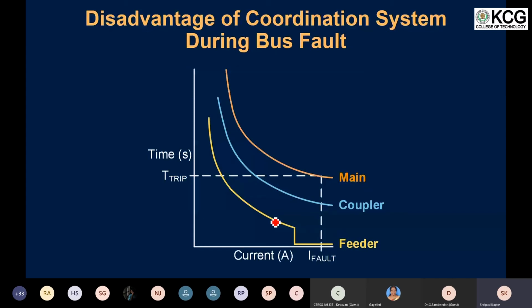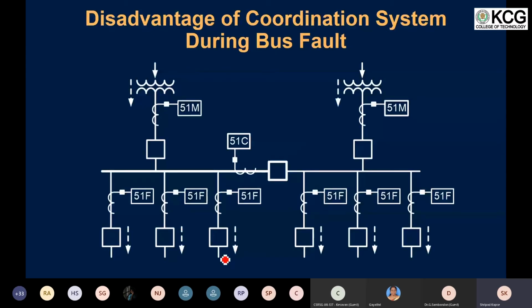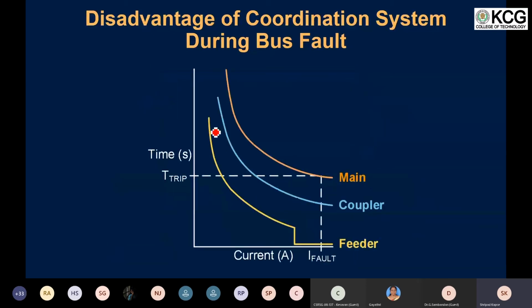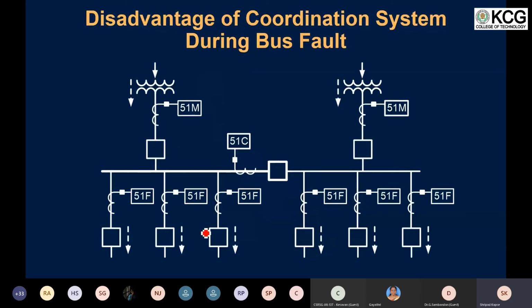For example, if a fault occurs on the outgoing side of a particular feeder, I would expect the breaker associated with that feeder to trip rather than the main incomer or the bus coupler, which is why we have a faster operating time for the feeder and a slower operating time for the incomers. If for some reason this particular breaker did not trip, we would expect the bus coupler and the main incomer relay to operate and trip the breaker.